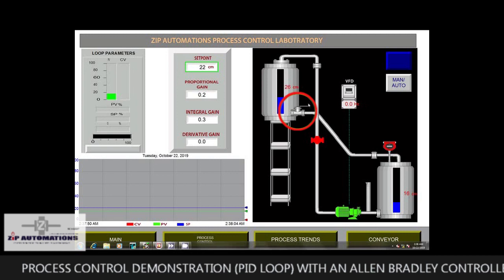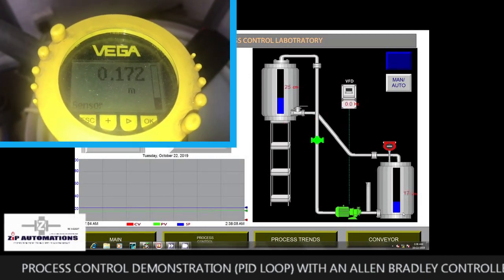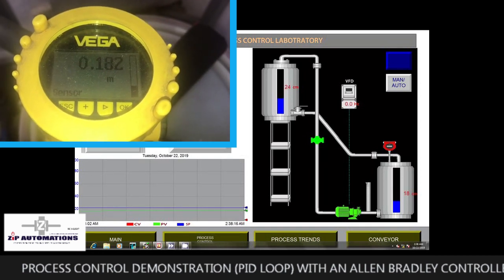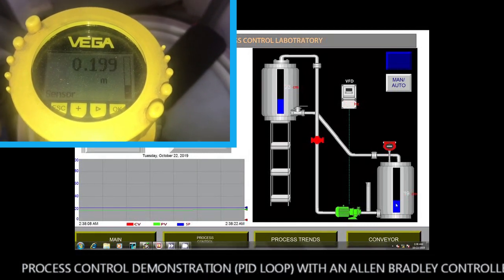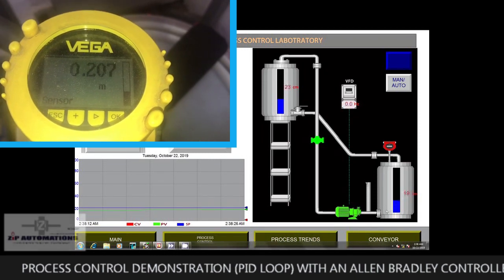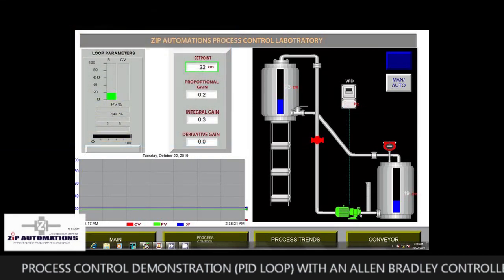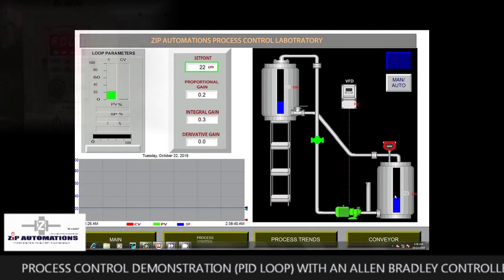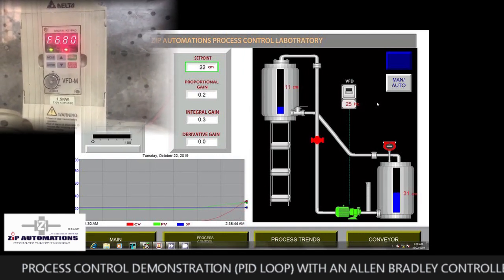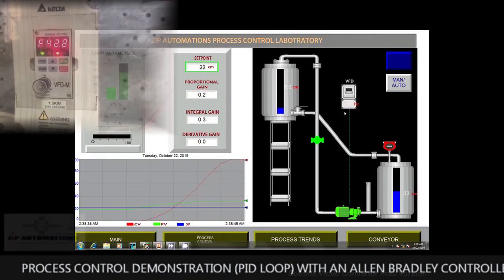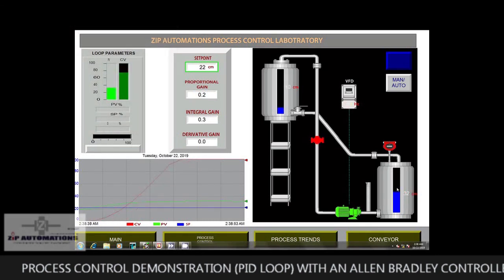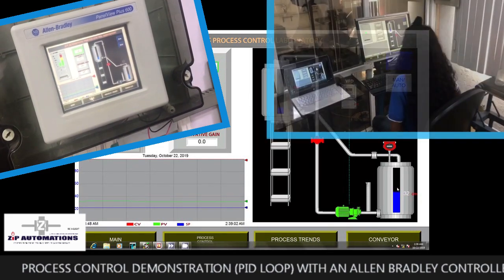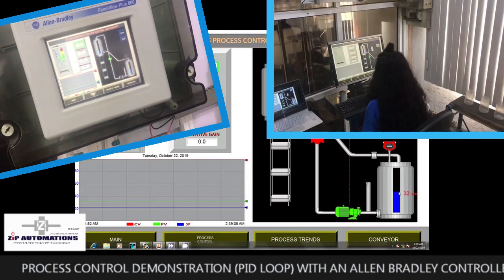Now this valve has been opened to cause a little bit of disturbance, and the level of our water is increasing. The process variable is rising, trying to get to the set point. So immediately it goes above the set point, our VFD will start to ramp up again and try to drain the water out of the tank. Now it's above our set point, our VFD is ramping up again and trying to drain water out of the tank. Our process variable is now reducing again, trying to get back to the set point.